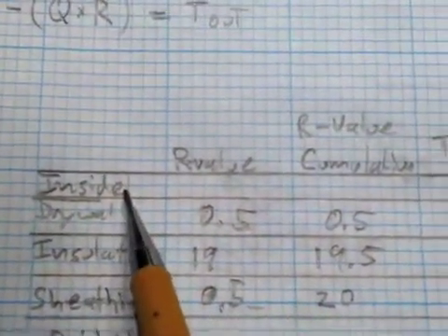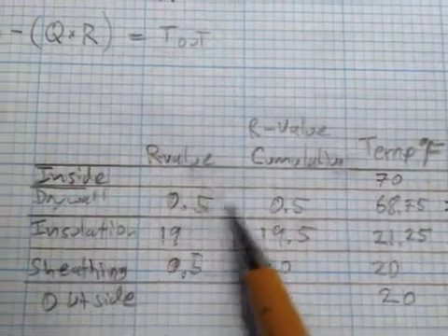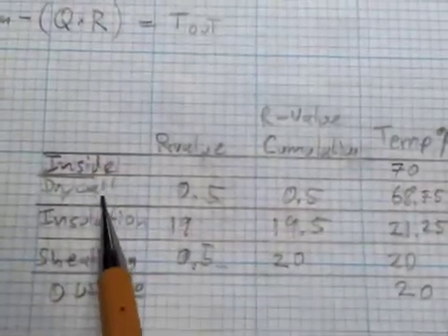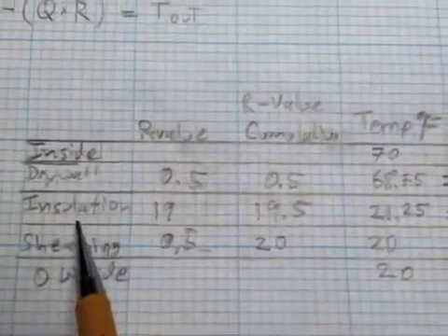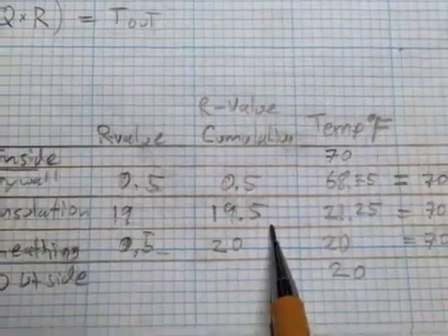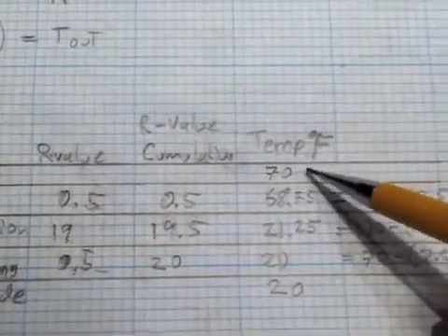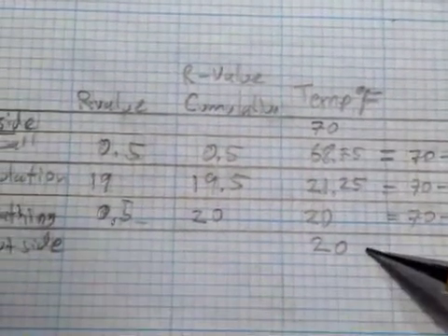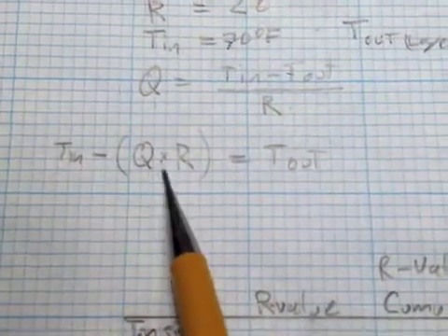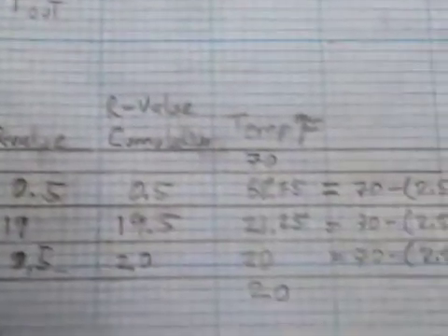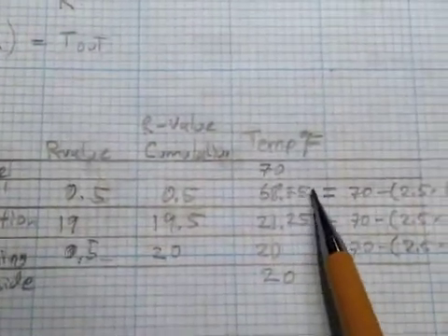Here's the table. We list inside temperature, then the R-value of each layer, the cumulative R-value going from inside to outside, and the resulting temperature. Drywall has R = 0.5, cumulative R = 0.5. Insulation has R = 19, cumulative R = 19.5. Sheathing has R = 0.5, cumulative R = 20. Inside temperature is set at 70°F and outside at 20°F. We apply the equation T_out = T_in − (Q × cumulative R) to each layer.